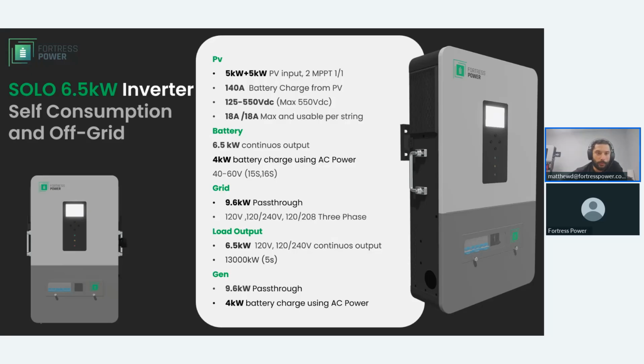Moving into the PV side, the inverter comes equipped with two MPPTs, 5 kilowatts each, where each MPPT has the capacity of charging the battery at 140 amps, okay? And it is very flexible in terms of the voltage. It does allow 125 volts to 550 volts DC, and 550 volts DC would be the max input voltage, say open circuit voltage, right? It uses a maximum of 18 amps, and it is the maximum, right? Can't go over that, 18 amps usable, okay?